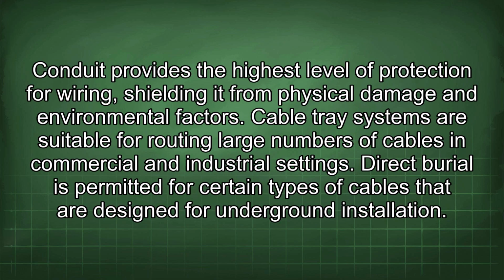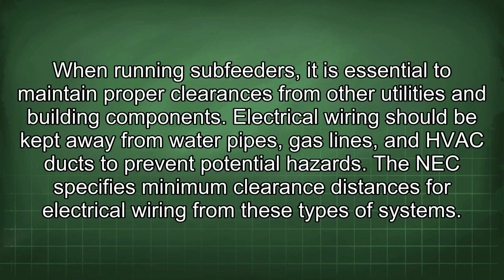Conduit provides the highest level of protection for wiring, shielding it from physical damage and environmental factors. Cable tray systems are suitable for routing large numbers of cables in commercial and industrial settings. Direct burial is permitted for certain types of cables that are designed for underground installation. When running subfeeders, it is essential to maintain proper clearances from other utilities and building components. The electrical wiring should be kept away from water pipes, gas lines, and HVAC ducts to prevent potential hazards. The NEC specifies minimum clearance distances for electrical wiring from these types of systems.